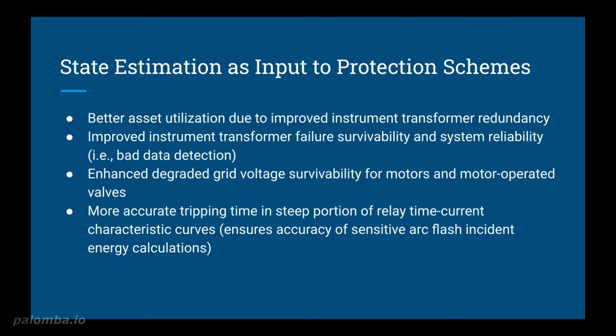Firstly, it should be recognized that using state estimation as input to protection systems can improve the system reliability by allowing better asset utilization and the use of redundant system measurements. Redundancy naturally improves system reliability. So additionally, this improves the situational awareness of the protective relays and increases the survivability of certain equipment failures, mainly instrument transformers and other sensing devices. This should become more clear when we take a look at our preliminary example on the next slide.